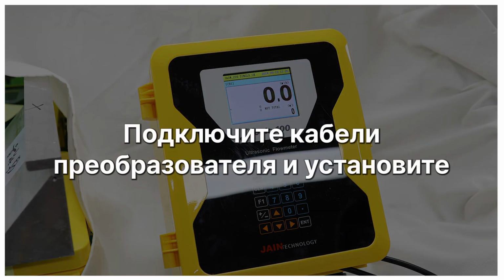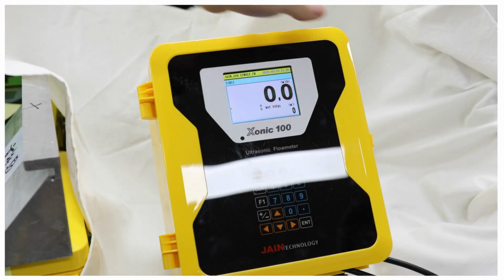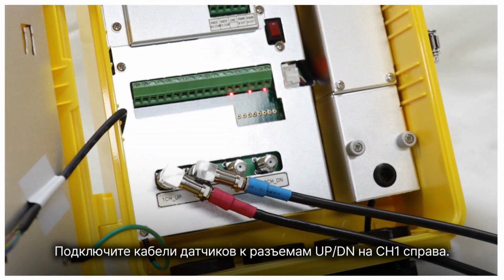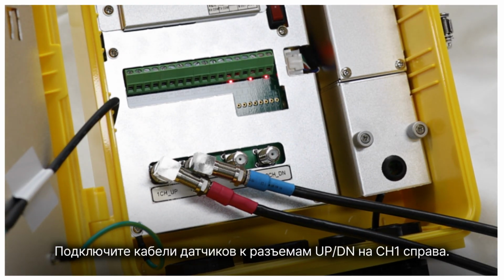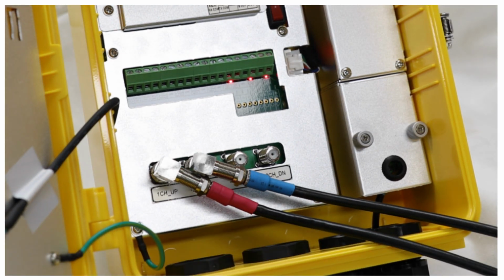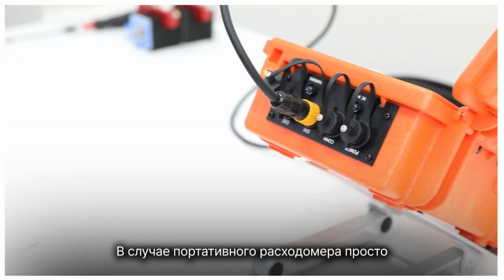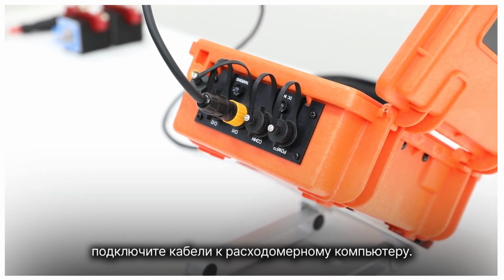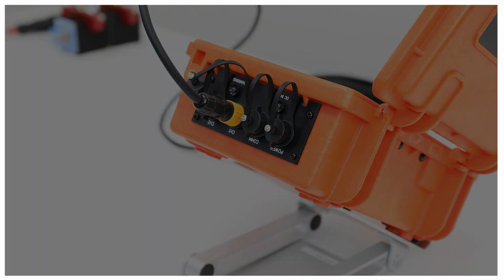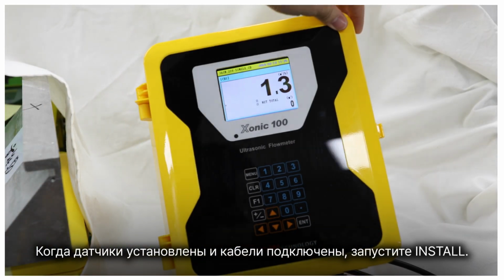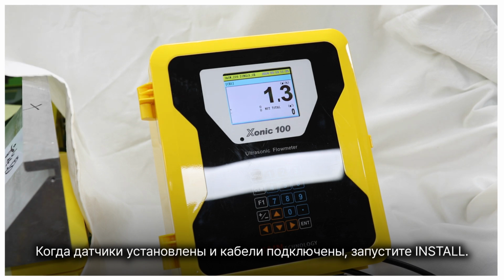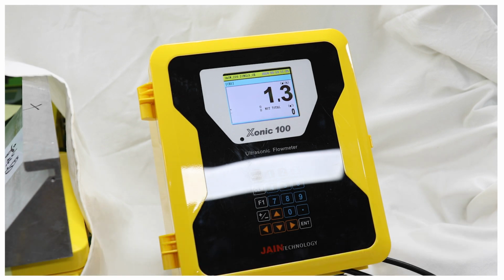Now, I'll explain how to connect the sensor cables and install the flow computer. Attach the sensor cables to the up and down connectors of channel 1 on the right. In the case of a portable flow meter, simply plug the cables into the flow computer. Once the transducers are installed and the cables are connected, start Install.